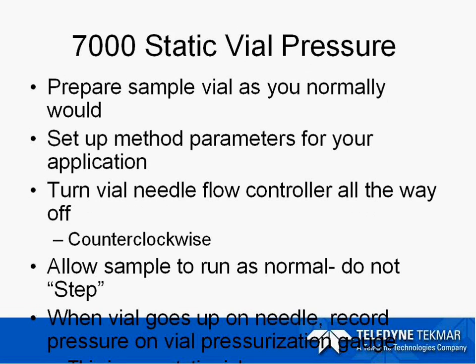Another important feature of method parameters for the 7000 is what the static vial pressure is. To determine the static vial pressure, you are going to prepare your sample just as you normally would and make sure all your method parameters are set correctly for the application. On the 7000 itself, you are going to turn the vial needle flow controller all the way off, which is turned clockwise. You are going to allow the sample to run, but do not hit step. When the vial goes up on the needle, you are going to record the pressure on the vial pressurization gauge. This is your static vial pressure.